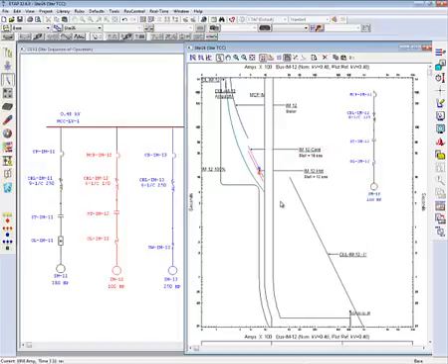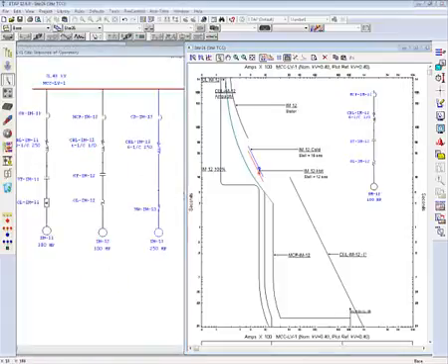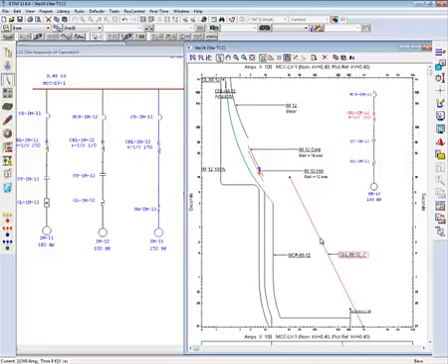Another important tool which helped me here to correctly view my one line star view is the combination of these protective devices' curves. So if you have two protective devices in series, you can combine them together to get an accurate curve of protection of this motor. We can also notice that the cable damage curve is protected, as it's not intersected by the MCP.